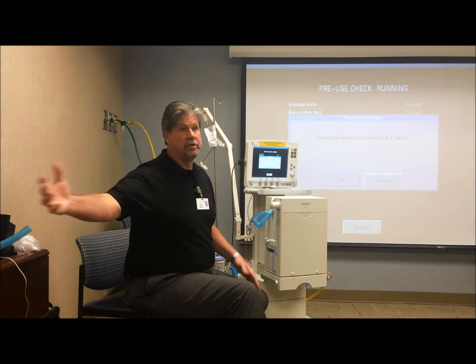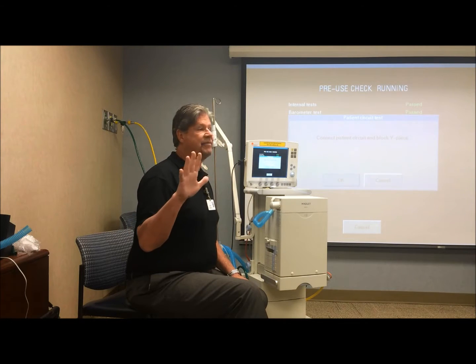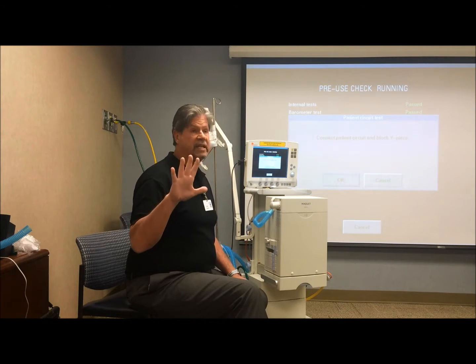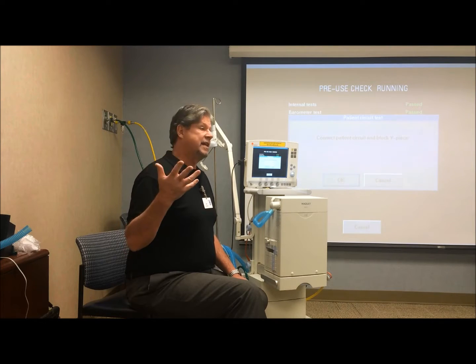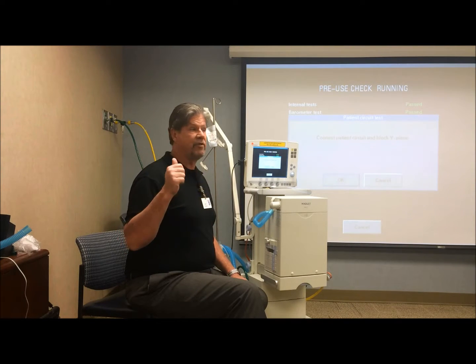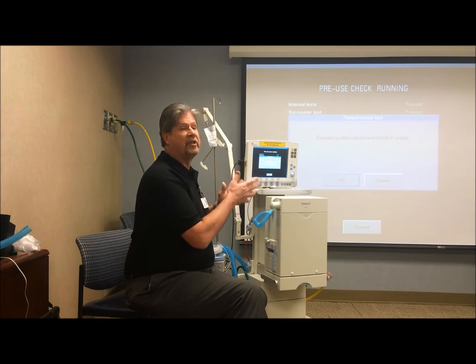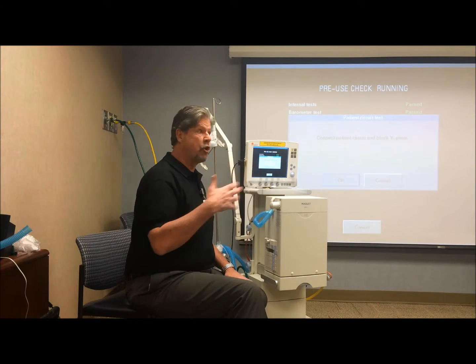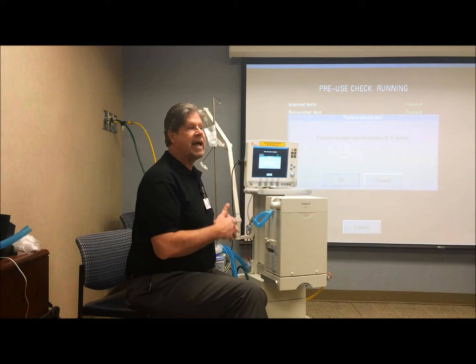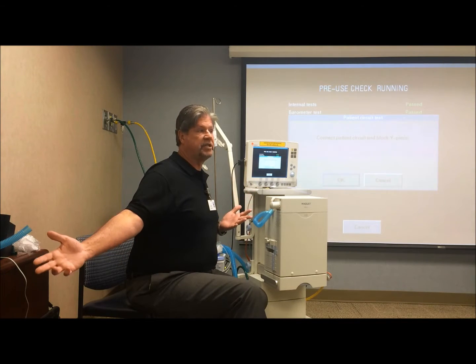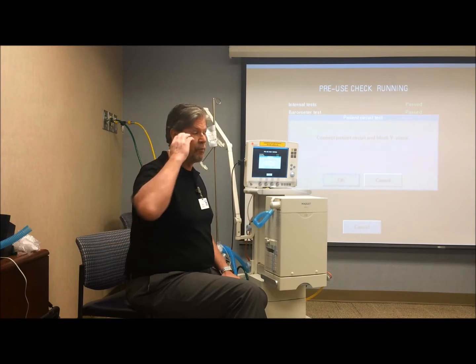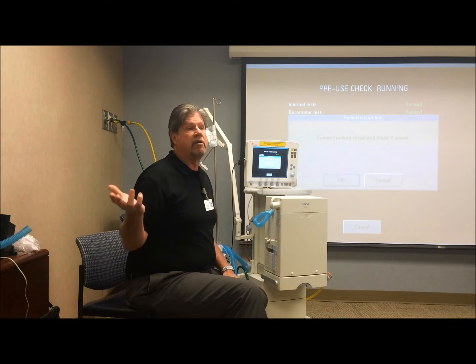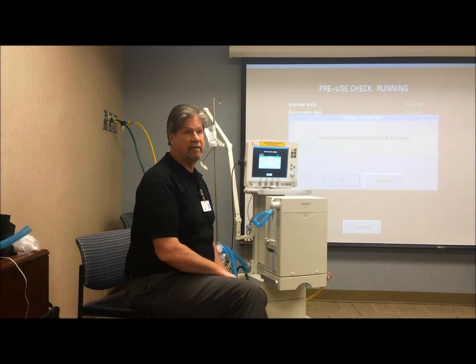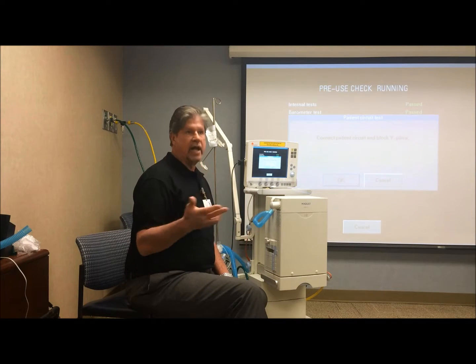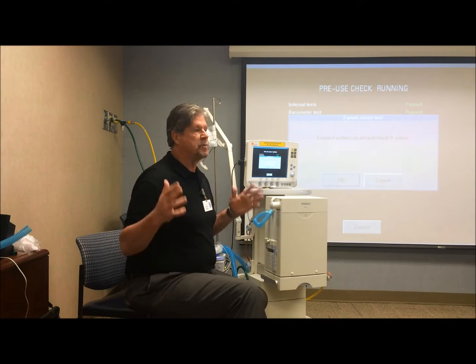So now you have a double circuit, so that means you're losing 4 to 5 cc's per centimeter of water pressure. So let's say it's 5 and your PIP is 25, you're losing 5 times 25 or 125 cc's to the circuit. So if you keep him on the same volume that he was enjoying in the ICU with one circuit, now he's only going to get 375 cc tidal volumes when you thought he was getting 500. Yeah, you've got to bump it up a bit. So, right, you have to bump it up by that much, but that's the principle.